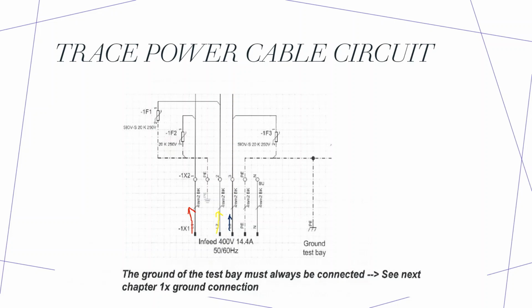So these three cables need to be connected with the PE. This PE acts as a ground for the input cable. It's for protection. And for the input protection, there are three varistors between the three phases and the PE, which is this one and this one. So all of these need to be connected to the ground also.